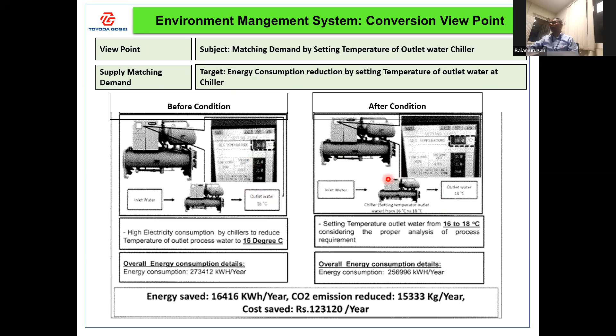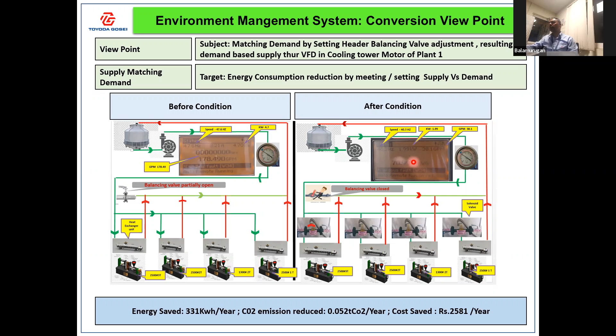Next is matching demand by setting header balancing valve adjustment, resulting in demand-based supply through a VFD on the cooling tower motor of plant 1. Here the target is energy consumption reduction by matching supply to demand. For example, it was operating at 178.4 gallons per minute, and now it is at 70 gallons per minute, through the VFD and also line balancing, that is valve balancing. So there is a big reduction. This also gives energy reduction. This again is an example for the conversion factor. These are all examples already done on the shop floor, which we are showing you.